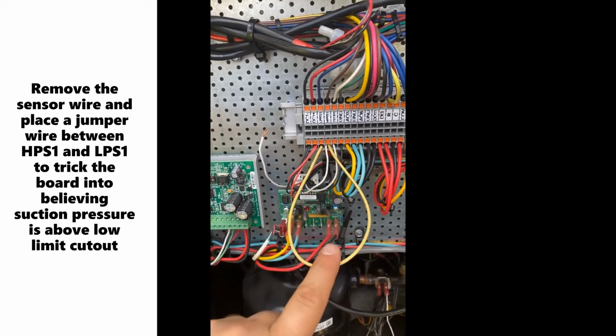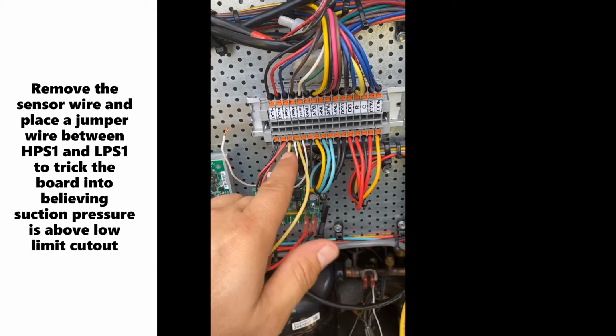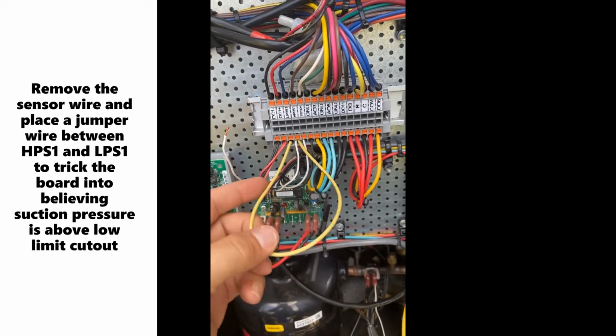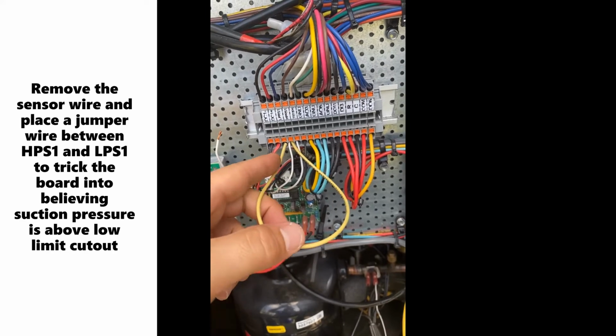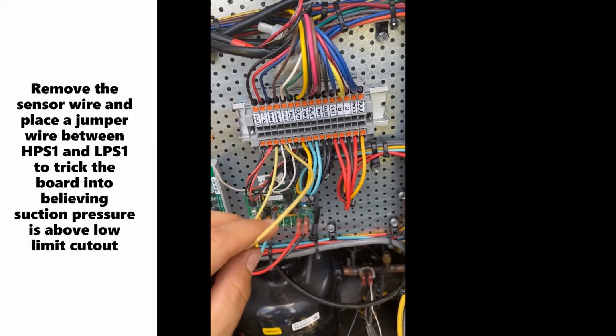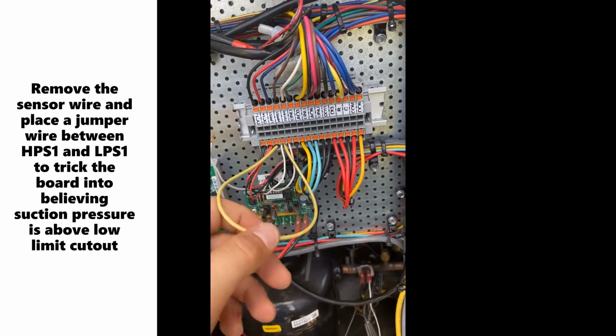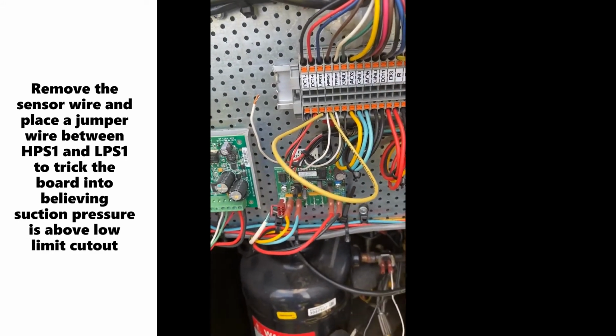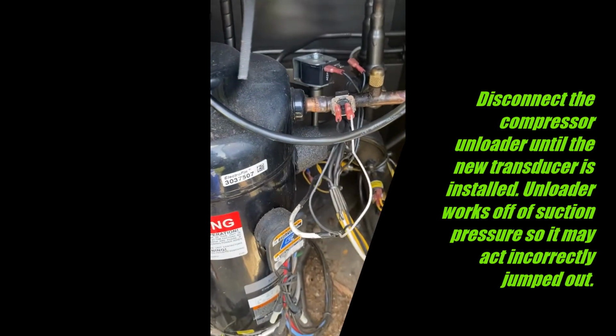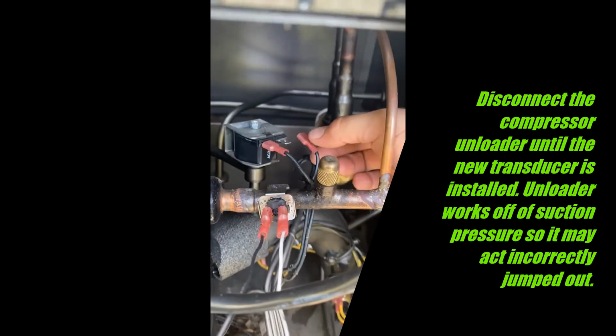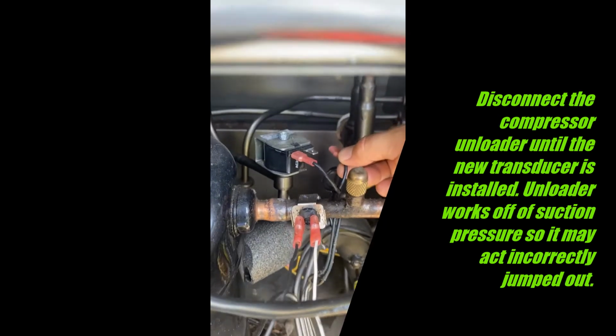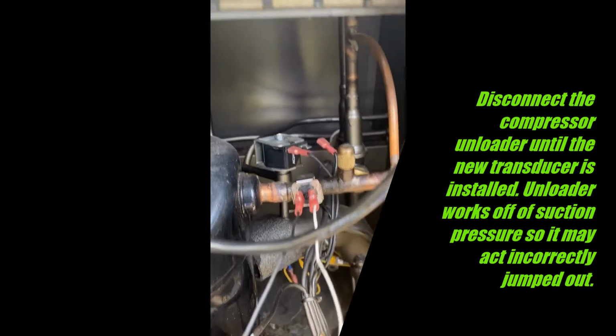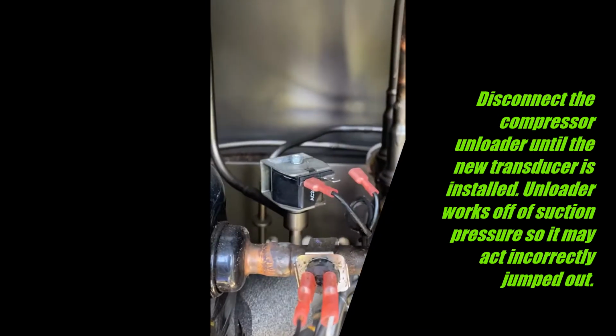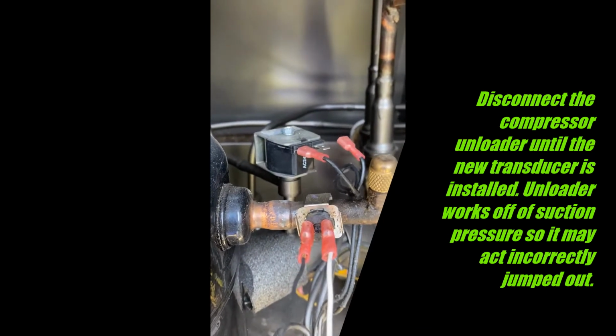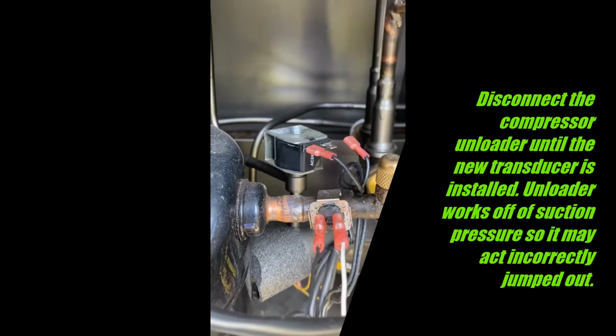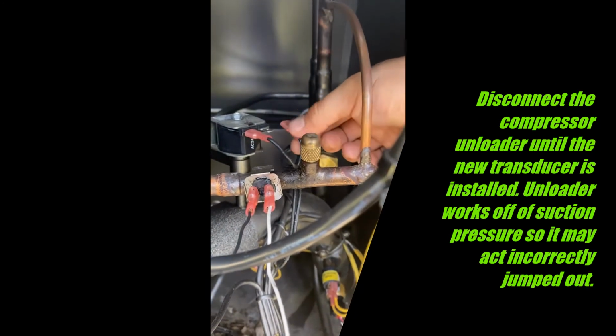So finally, I put a jumper from the high pressure transducer feeding the low pressure transducer, just to trick it to think that it's not below the point of cutout. And it's been running just fine like that. Also, when you jump it out, you need to disconnect your unloader from your compressor. You can see it comes out of the suction line, and it's got a solenoid on top. This is controlled by the suction transducer, so you just disable it. It'll be fine until you replace the transducer.